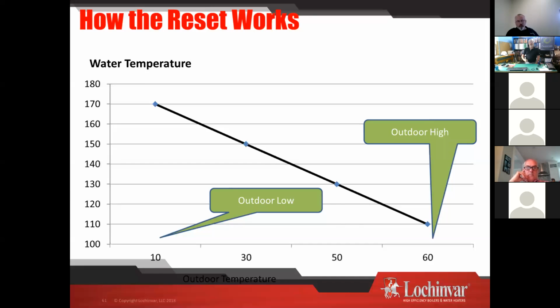We just pick up a few extra therms of savings every year, and that's the important point of these, getting those extra therm savings. So in this case, my outdoor low is set for 10 degrees. So at 10 degrees out, I'm going to go to 170 degree water. Why 170? Because we have a 10-degree offset. So 170 will get you to 180.